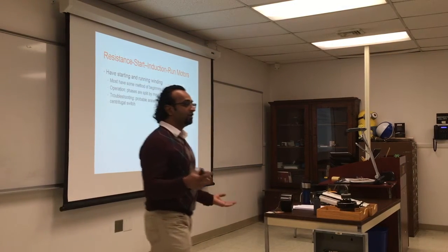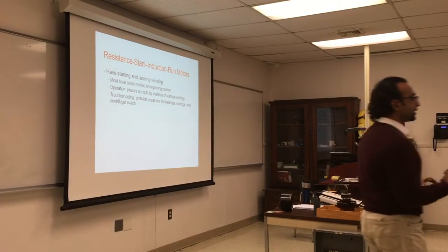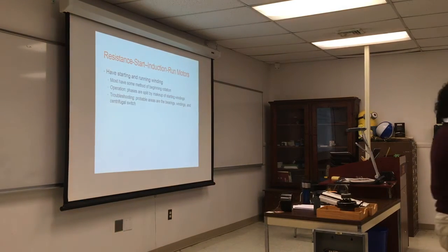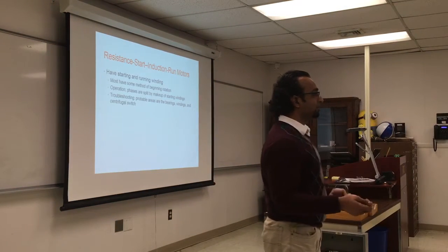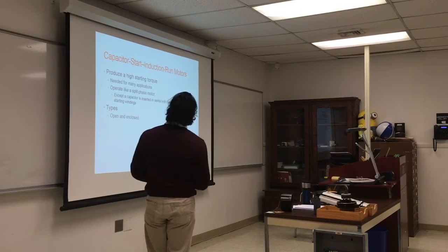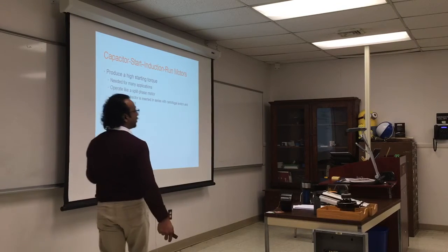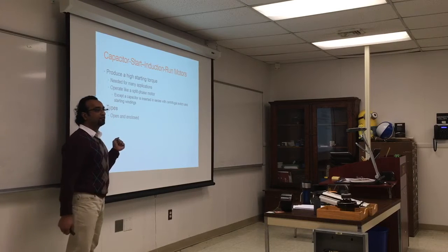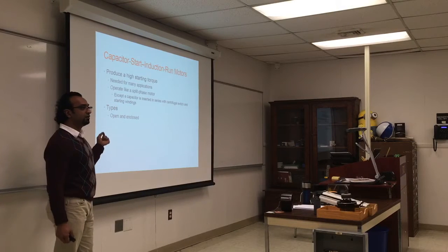Troubleshooting, we did the troubleshooting already. So basically go look at the switches, look at the winding, and make sure nothing is frayed, coming apart, or touching the casing. Capacitor start, induction run motors, those only have a capacitor. They do not have a start capacitor and a run capacitor.